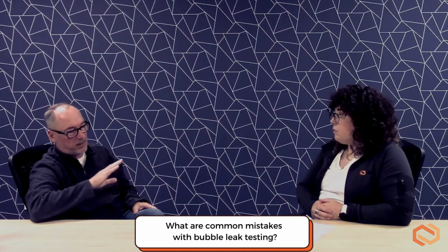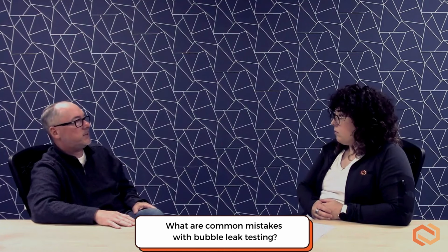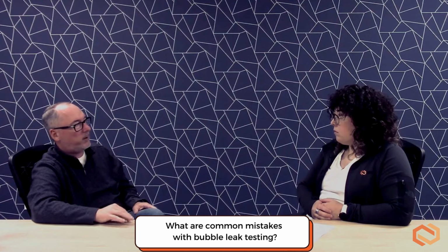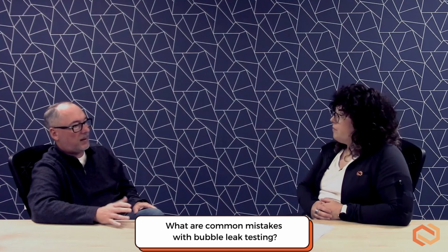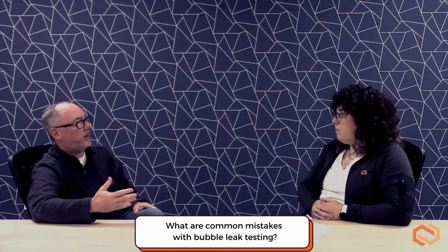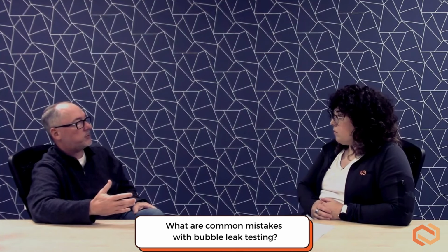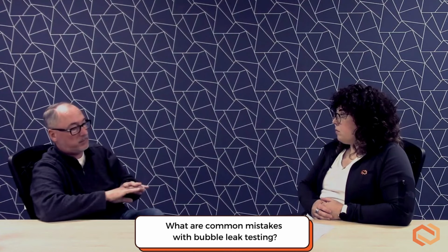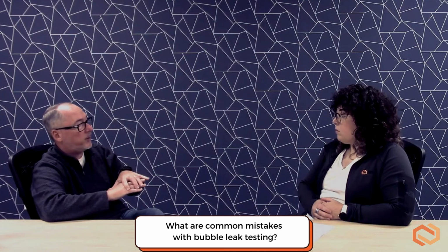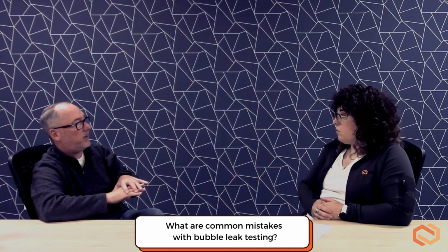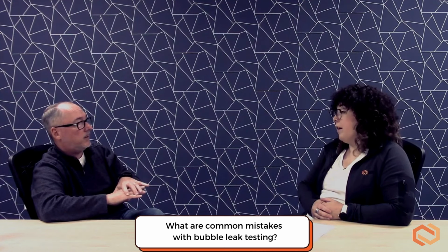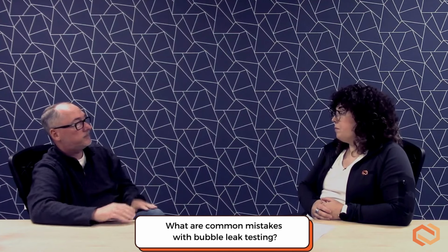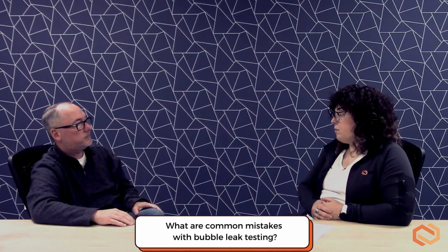It's great for puncture resistance, it's great for abrasion. Where we run into the problems the most is on the Mylar, the poly, the nylon, the film side. We primarily run into the issues there, not so much on the Tyvek. Occasionally it will happen where, like I said, a tortuous path will open up a little bit. That doesn't necessarily mean that a microbe can get through there. Right. It means the air is escaping in a steady stream. That makes sense.